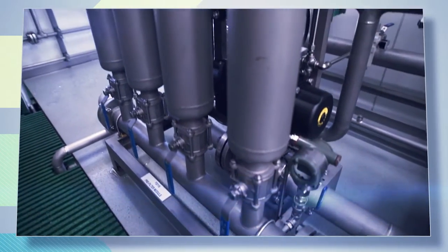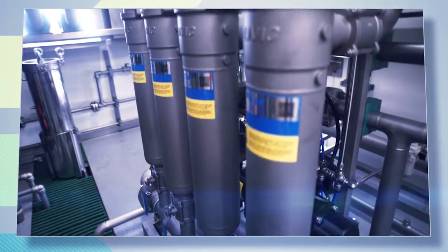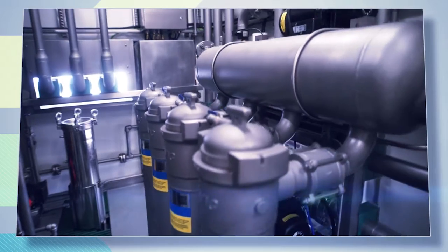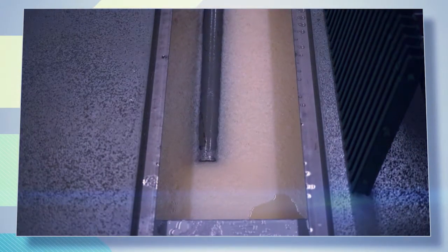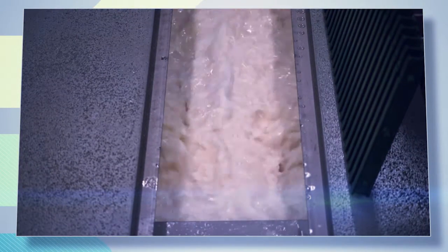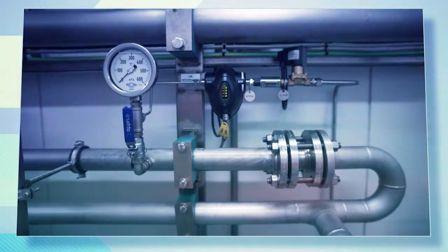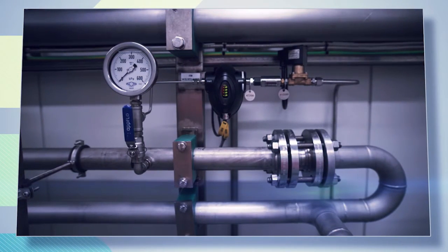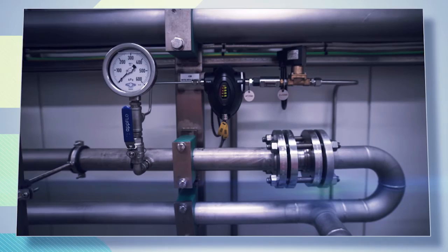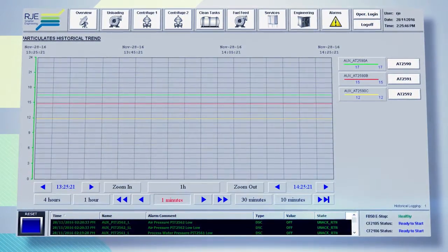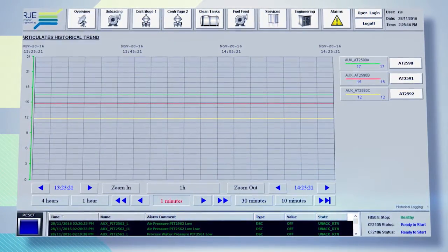A pre-filter module is available for initial filtration of raw fuel received from tankers or bulk supplies. The filter employs surface-style elements that automatically backflush when required. Fuel particle monitors can be supplied to provide ISO 4406 code data and long-term trending of fuel particulate levels.